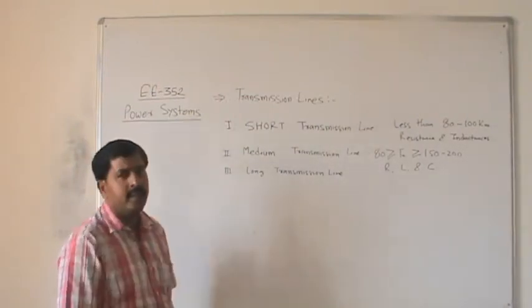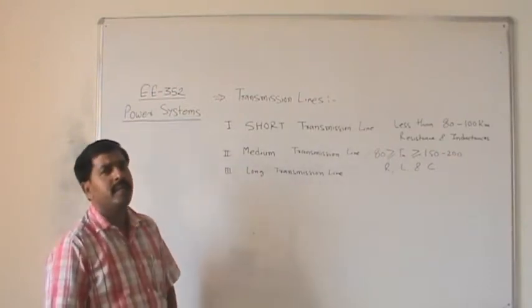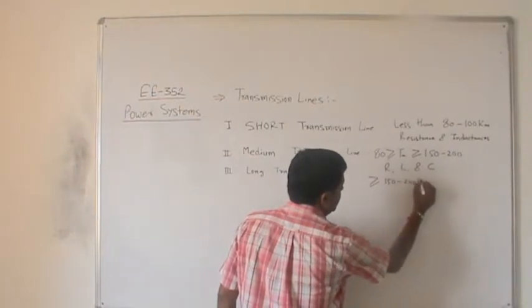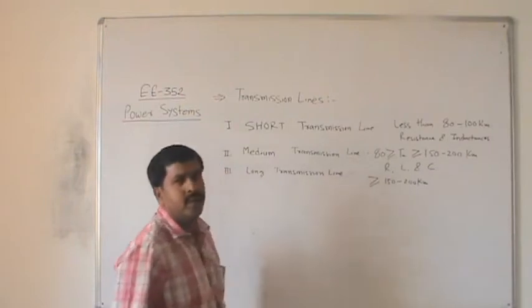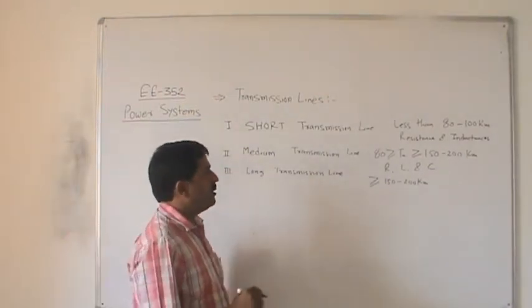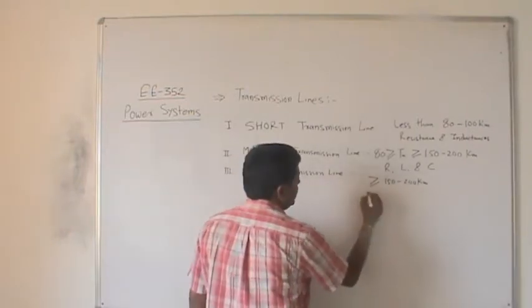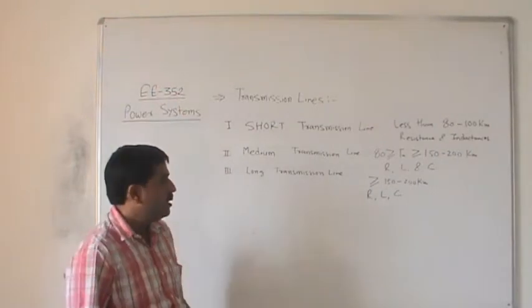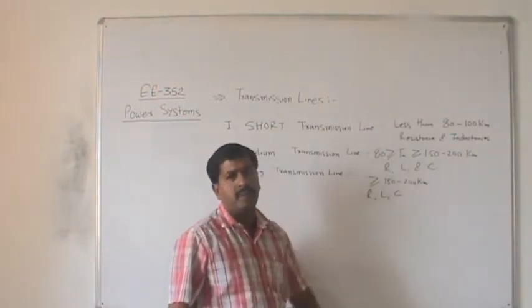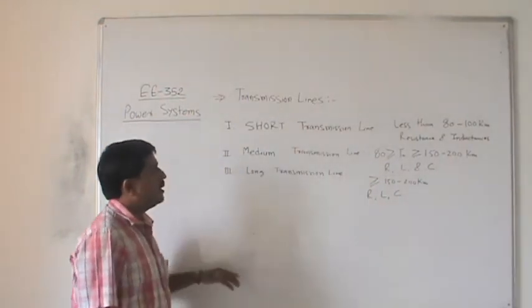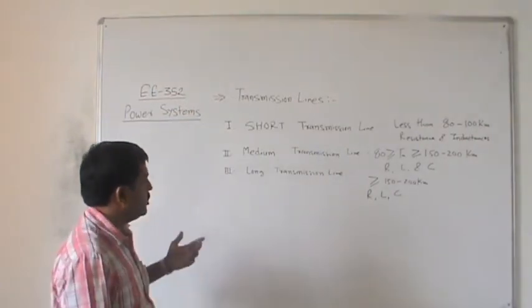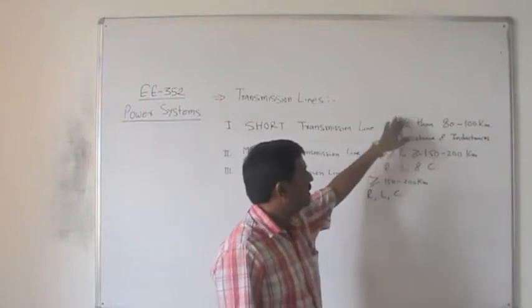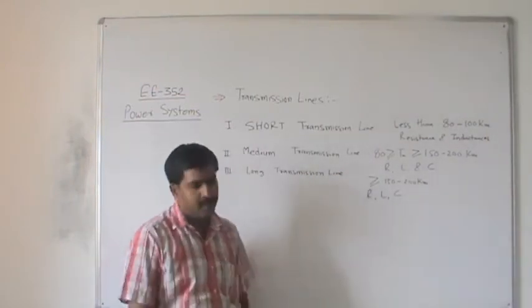For the long transmission line, if the length is more than 150 to 200 km, it is termed a long transmission line. For its analysis, we take resistance, inductance, and capacitance, and the capacitor is treated as a distributed parameter. So there are three types: short, medium, and long, depending upon the distance.